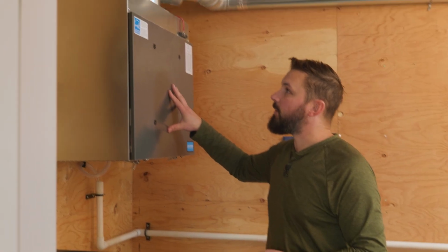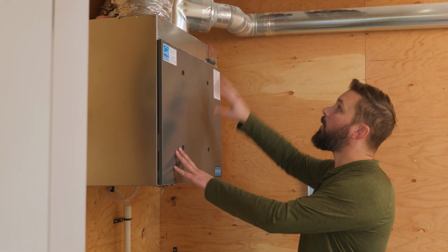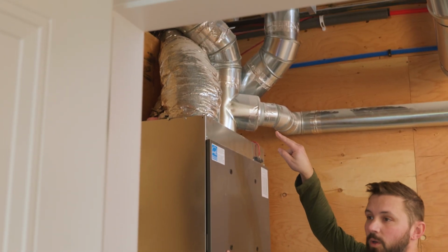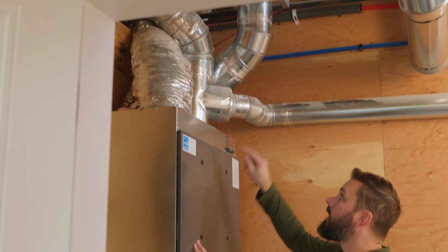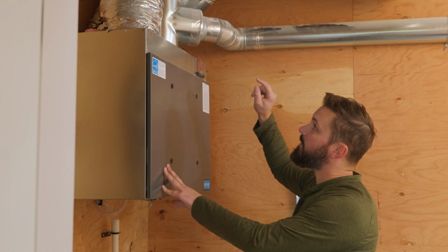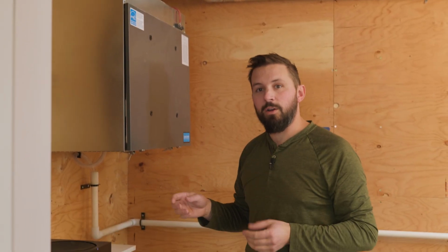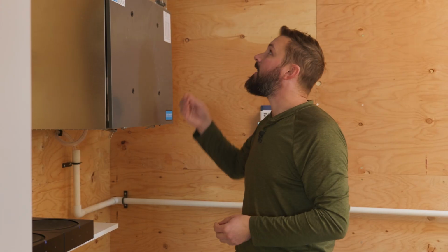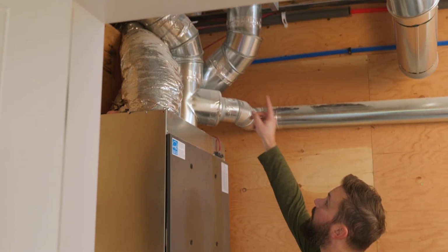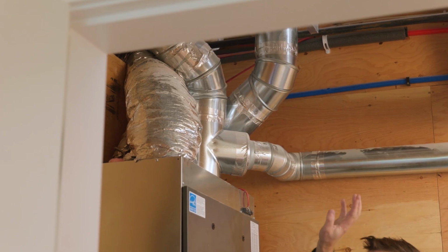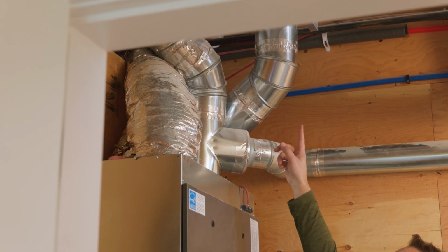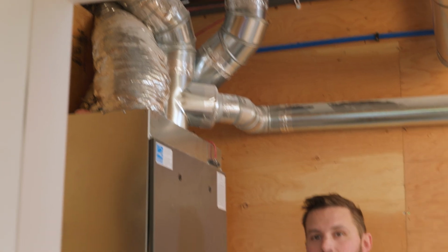If we look at the HRV that we have installed in this home here, we have 4 pipes coming out of the top of it. 2 of them go to the outside, 1 for bringing in fresh air and 1 for expelling stale air. The other pipe networks go to the different areas of the house. We're drawing exhaust air from dedicated portions of the house to remove that air from the home, and then we're supplying via this pipe up here fresh, filtered outside air that's had the heat recovered from the outgoing air to our return air plenum for our furnace. The furnace then takes that air and distributes it throughout the house.